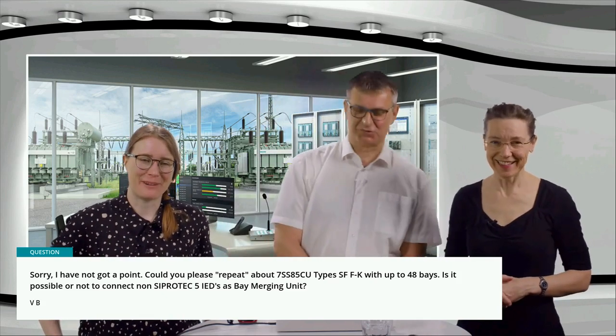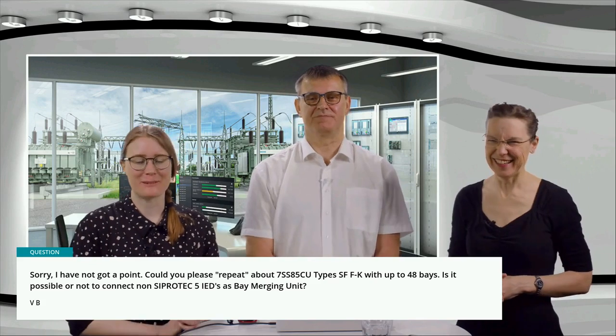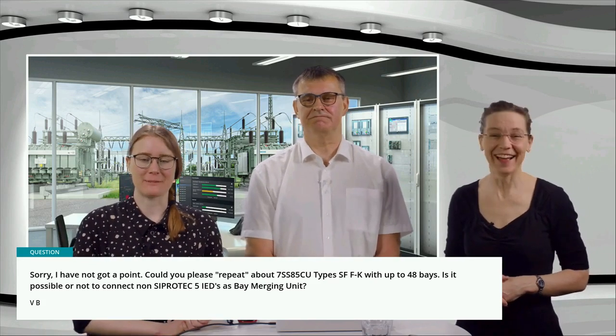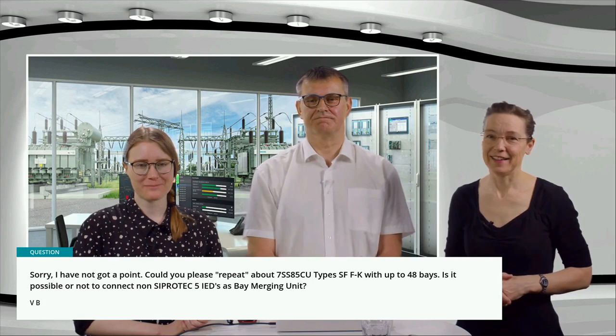I can take it. For the 7SS85CU solution, you can connect modular SIPROTEC 5 devices. And for the IEC 61850 compliant. Can you go back to the question? Is it possible to connect non-SIPROTEC 5 IEDs? No, this is not possible. This would only be possible with the IEC 61850 compliant solution.